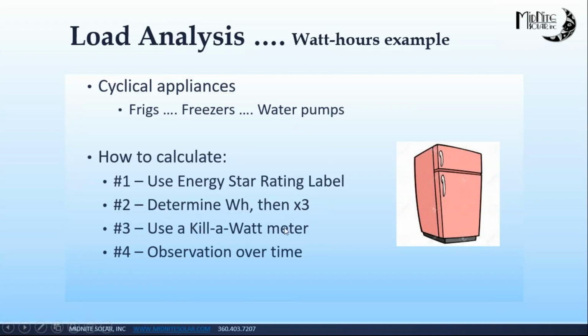You could use a Kill-A-Watt meter—plug it in between the extension cord on the refrigerator and the wall. The meter counts up and shows you the amps, the voltage, the total wattage consumed. So over a 24-hour period, you come back to that meter and it'll tell you the actual number of watt hours that appliance consumes. Then you can take that Kill-A-Watt meter over to the next appliance, and maybe over a week's time you can derive your full load analysis.